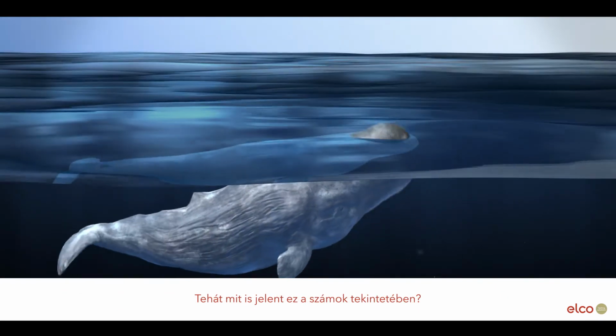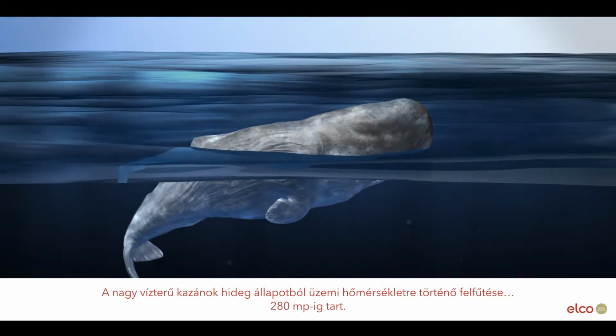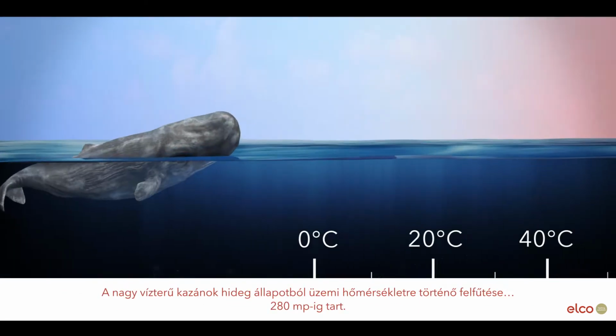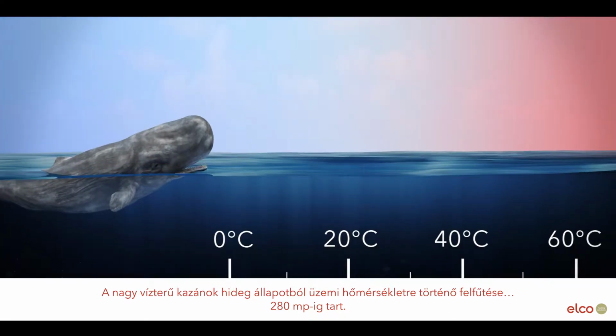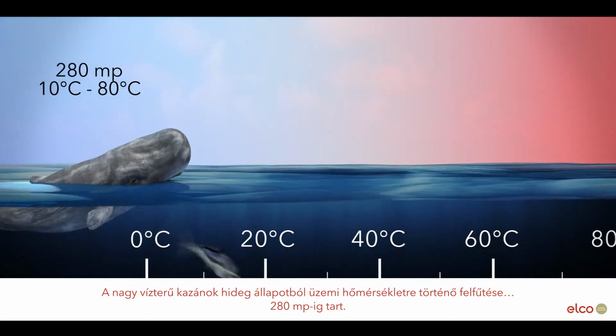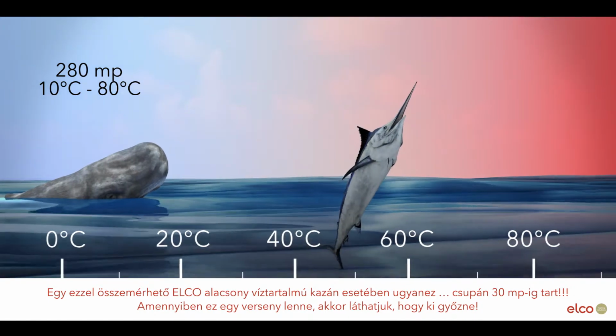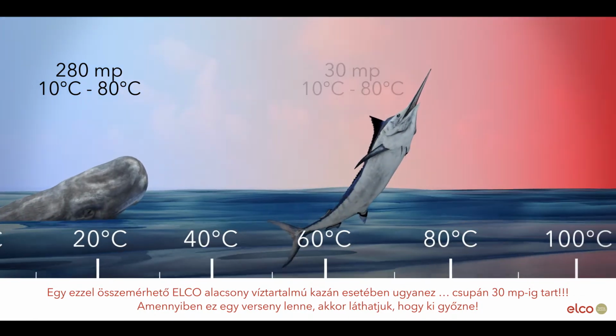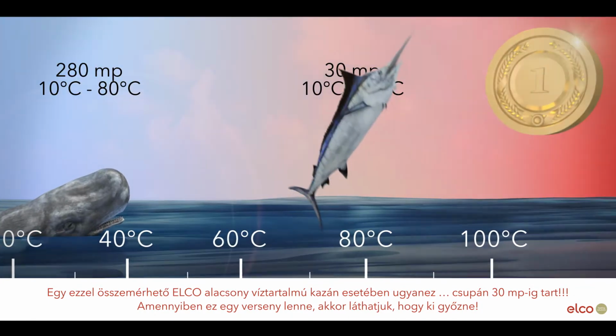So what does this mean in terms of numbers? The time needed to get a high water content boiler from cold condition to standby temperature is 280 seconds. A comparable ELCO low water content boiler needs just 30 seconds. If this was a race, you can see who is going to win.